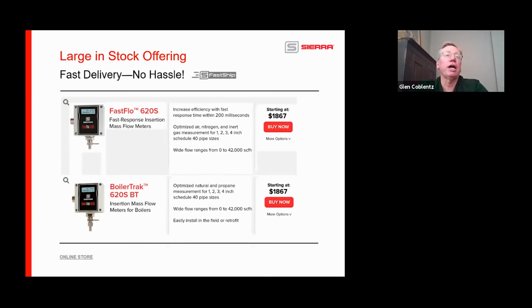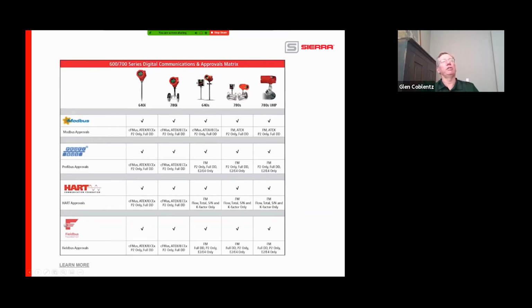But you could, if the customer has flexibility, you sell them one calibrated to a 4-inch pipe and you use a K-factor capability from 0.5 to 5 to resize the area of the pipe that meter thinks it's measuring to give them a ballpark measurement. So as long as you have a customer that's a little flexible with what their expectation is in accuracy, there's a couple ways that you can solve the problem at that point in time. So again, you're adding in a fairly large derate by going from 4 to 6 inches, but at least he's making a measurement. And maybe that's good enough for him at that point in time, based on the other things that he's having to deal with.